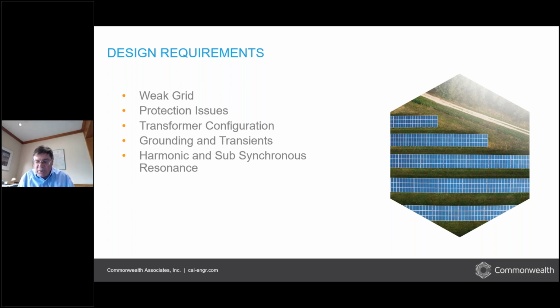Transformer configurations are very, very important. There are two transformers that you need to know the configuration for. One is the plant transformer that typically converts the output of your plant from your collector voltage, typically 34.5, to whatever the transmission voltage is. I've done a project, for instance, where the conversion was from 34.5 to 46 kV. So not a big step, but still there was a transformer there that was in a very weak system, and there were concerns, to the point of not being able to interconnect the project, about weak contribution from the grid under the contingencies that lines were lost. That problem was resolved. Last I knew, the project is in operation.